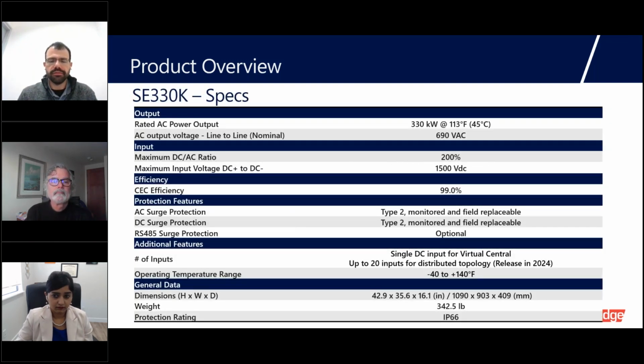Some more specifications here. I'm not going to go through them one by one, but if you have any questions, again, let us know. The summary is a 330 kW inverter, or kVA, up to 45 Celsius or 113 Fahrenheit, 690 volts AC, 200% DC to AC ratio. As mentioned before, it's 1500 volts. We have AC and DC surge protection similar to what we have on the Synergy units.